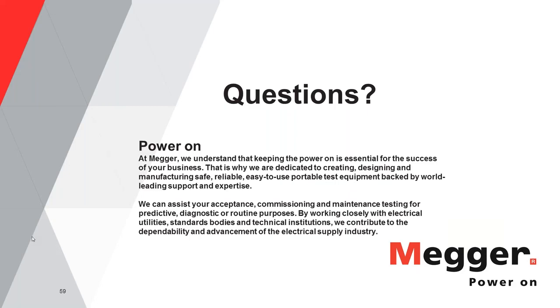That's a very good question, because obviously if we can cut down the number of tests, it would certainly help us improve efficiency and make sure that we get the job done quickly. But think of this from a system standpoint. When we talk about primary injection testing versus secondary injection, if you do the secondary injection testing, you can still verify that the trip unit is working, but in reality, you're not checking the complete system, which is the breaker operation and the operation of the trip unit.